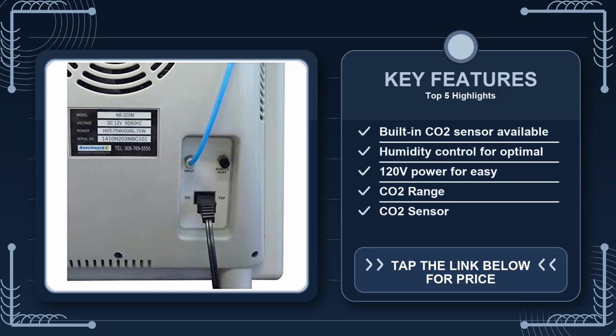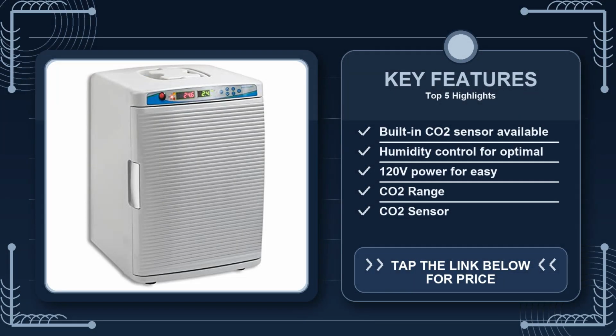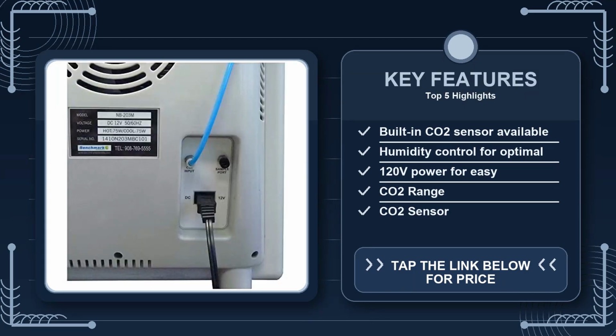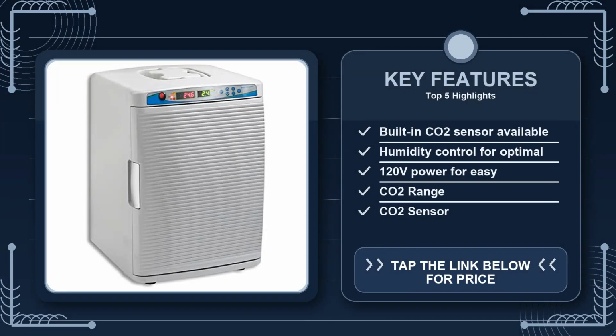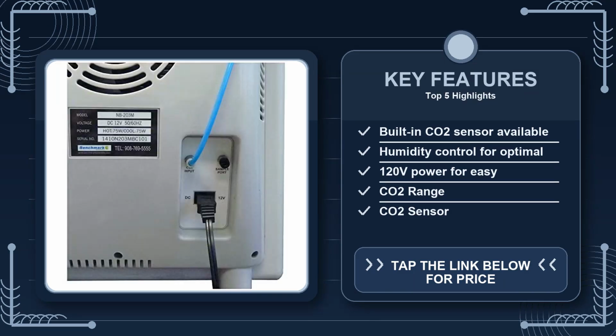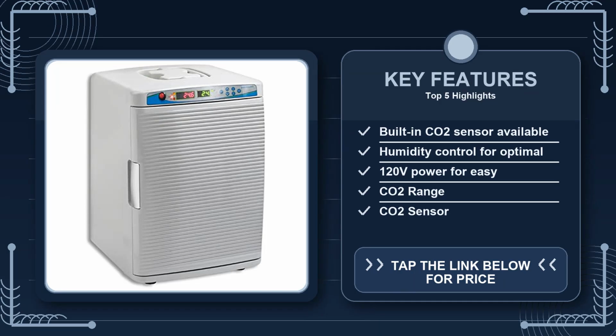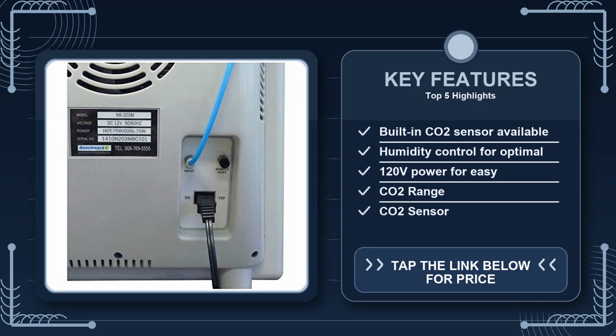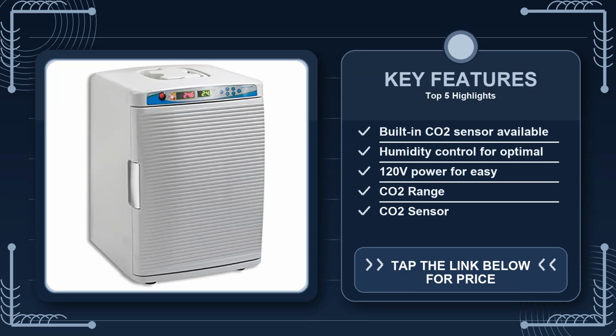Another real-world benefit is the built-in CO2 sensor. Many entry-level incubators rely on an external sensor that you have to attach and calibrate separately. With Benchmark's internal sensor, the calibration is done right inside the chamber, and the system runs its own checks to warn you if the reading drifts. In practice, that reduces the chance of a silent failure that could ruin weeks of work. I also appreciated the quick-read LCD panel on the front. It shows temperature, CO2, and humidity at a glance, so you can verify the conditions without pulling a laptop out to query the machine.